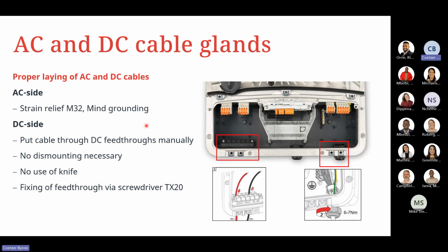So on the AC and DC cable glands, we have a proper laying of your AC and DC cables. On the AC side, we've got a strain relief M32, but you can mount the grounding with the gland itself. On the DC side, we've got push through DC feed throughs that are manually pushed through. So very similar to the old snap inverters where you had a plastic stopper with a rubber push through for the screws itself. And then we'll use the strain relief. Lastly, once we've done all our connections coming in on the DC side, we then fasten the strain relief to prevent anyone from being able to pull the cables physically out of the unit at the bottom here.